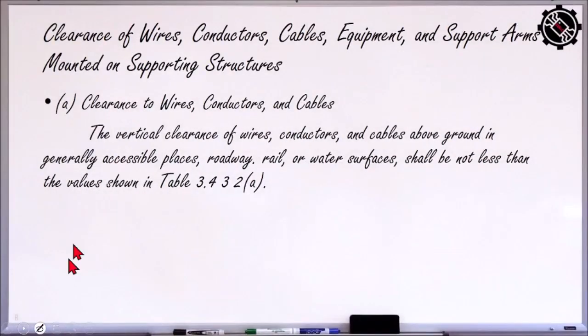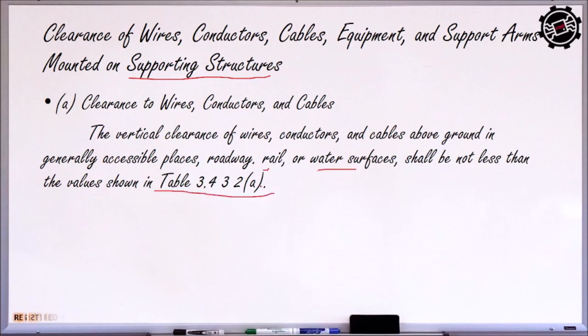Okay. So clearance of wires, conductors, cables, and support arms mounted on supporting structures. So clearance to wires, conductors, and cable. So the vertical clearance of wires, conductors, and cables above ground in generally accessible places, roadways, rail, water surfaces shall not be less than the values shown on table. So, ito na yung table na sasabi ko. Table 3.4.3.2a.